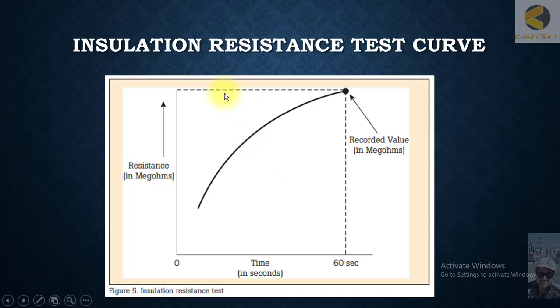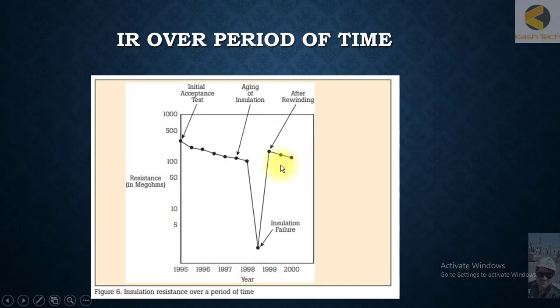Looking at the insulation resistance test curve: when you apply the voltage, the charging current slowly decreases, and the recorded megaohm value increases gradually. After approximately 60 seconds, you will get stable and proper results.